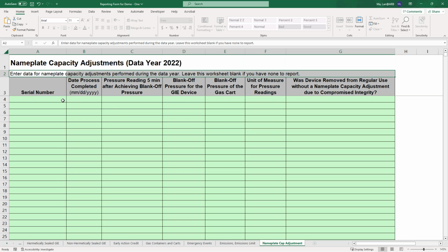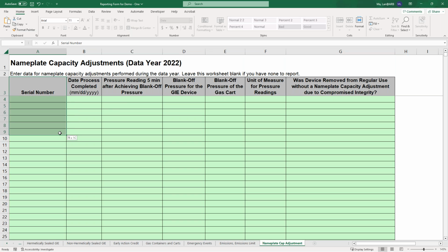If you performed any adjustments, you'd enter the serial number of the device in column A, the date the process was completed in column B, and several pressure readings which are required to be recorded while performing the process in columns C through E. Those are the pressure reading 5 minutes after achieving blank off pressure, the blank off pressure of the GIE device, and the blank off pressure of the gas cart, respectively. Note the term blank off pressure is defined in the regulation. You can report these pressure values in any unit you like as long as the unit is the same, which you must report in column F.